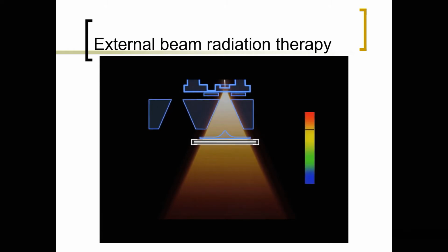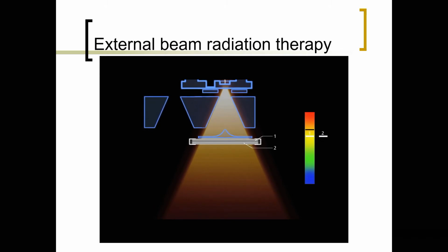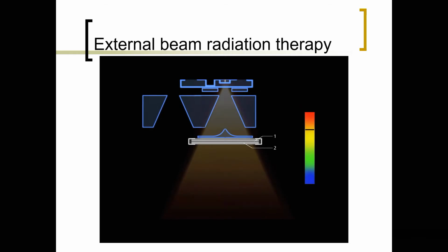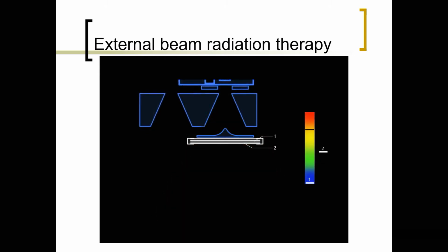The dose delivered to the patient is measured and controlled simultaneously in two independent ionization chambers. One chamber is the primary dosimeter. It measures the radiation and terminates the beam when the required dose has been delivered. The secondary ion chamber acts as a backup and will stop the irradiation if the primary chamber fails.